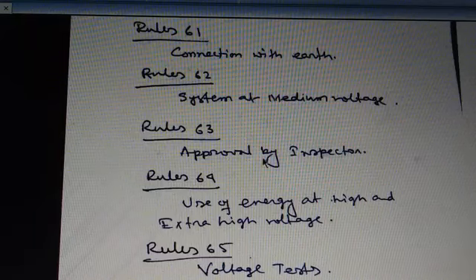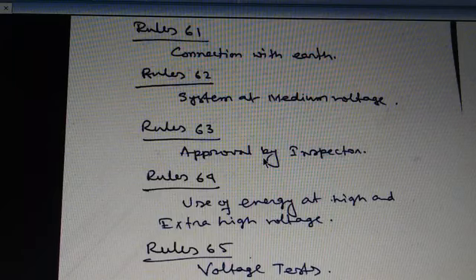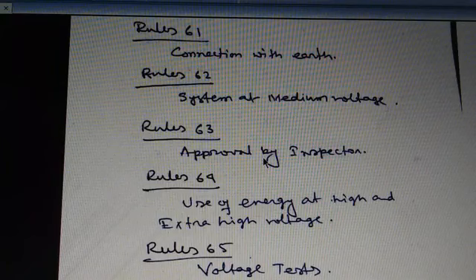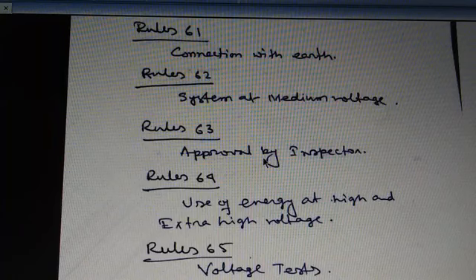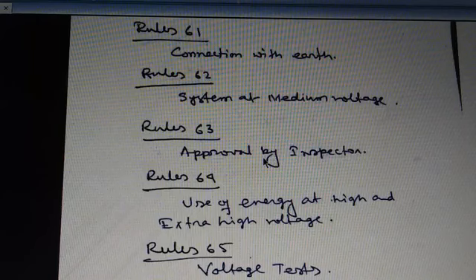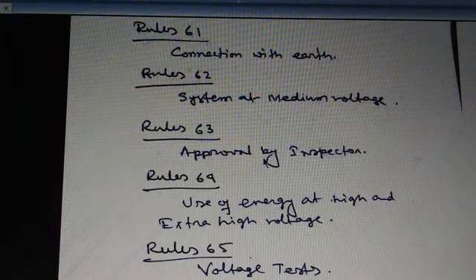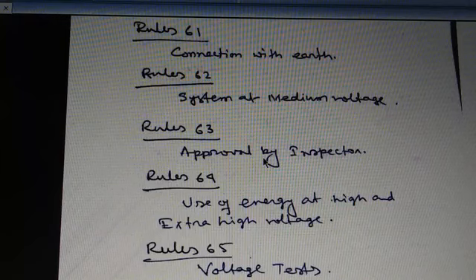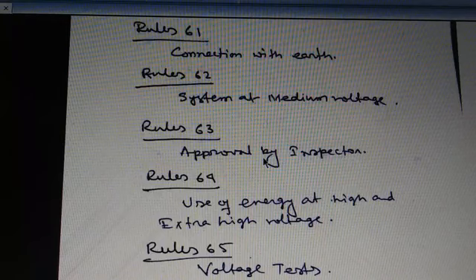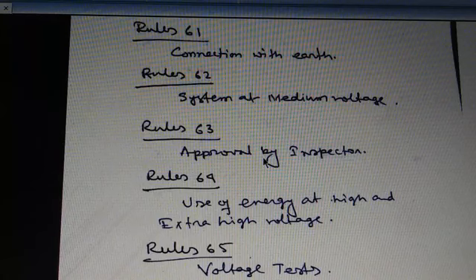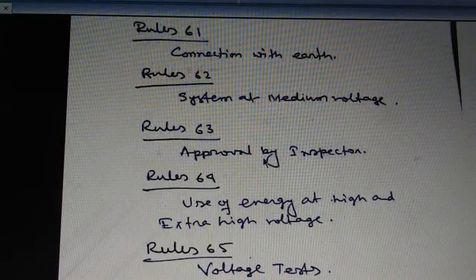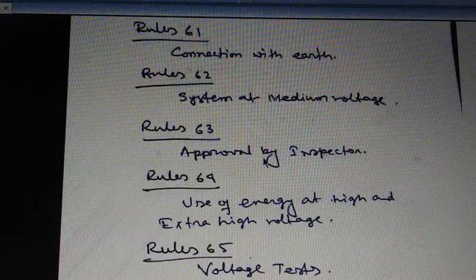Rule number 63, approval by inspectors. Before making an application to the inspector for permission to commence supply of energy at high and extra high voltage to a person, the supplier shall ensure that the high or extra high voltage electric supply lines or apparatus belonging to him are placed in position properly, joined and duly completed and examined. The supply of energy shall not be commenced by the supplier unless and until the inspector is satisfied that the provisions of rules 65 to 69, both inclusive, have been completed and the approval in writing of the inspector has been obtained. Next, rule number 64, use of energy at high and extra high voltage.